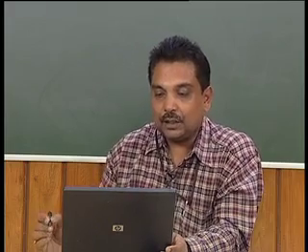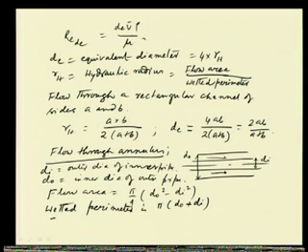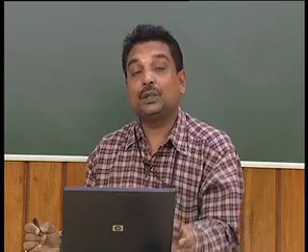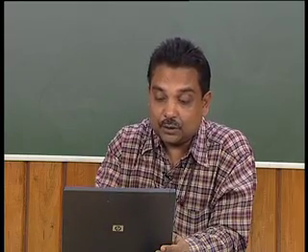Therefore, for this case, if we do the calculations, we get flow area by wetted perimeter, so the equivalent diameter is actually dO minus di. This equivalent diameter, dO minus di, is used for calculation of the hydrodynamic situation, that means for calculation of pressure drop.